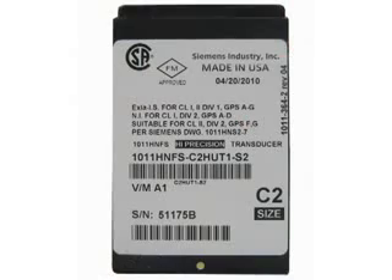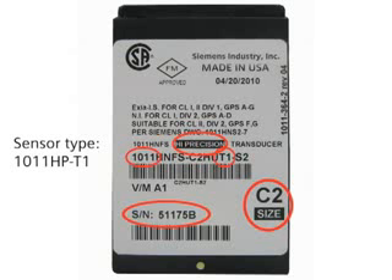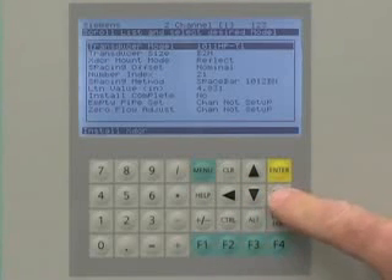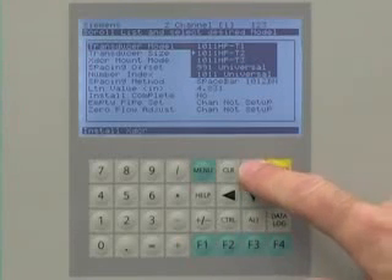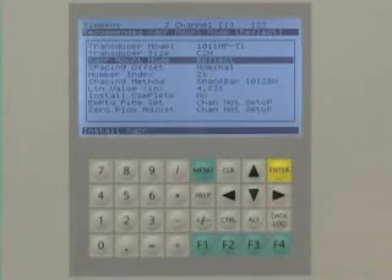Now we will enter the sensor data into the SITRANS FUS1010. This will help us mount the sensors for optimal performance. The data we need is the sensor type and size, which is on the sensor label. Since the sensors are supplied as a matched pair, verify that they have the same serial number followed by an A or B. To enter the sensor data, navigate to the Install Transducer screen and from the drop-down menu, select the sensor model and size. The SITRANS FUS1010 will recommend the most suitable sensors for the application — select the size matching your sensor.